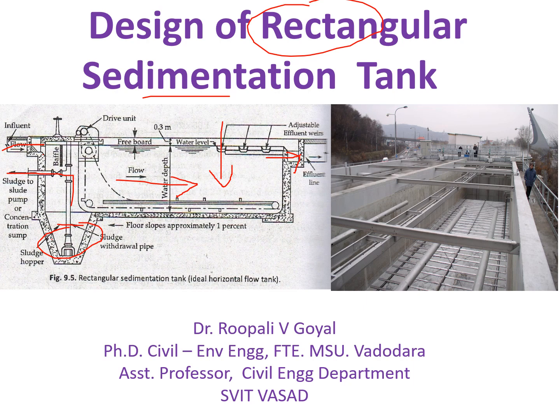So the vertical velocity is related to your SLR, surface loading rate, and that is equivalent to your settling velocity. And when we take horizontal velocity we get a cross sectional area, which means depth into width, that you have to remember.